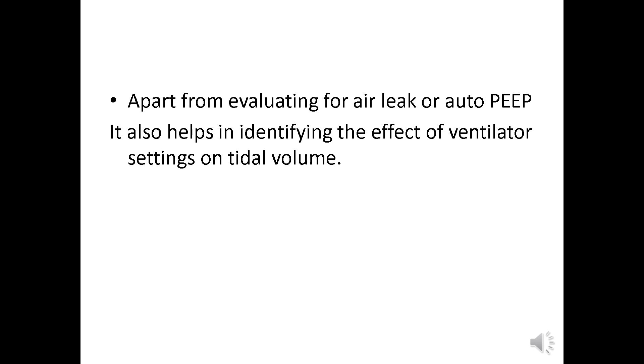Apart from evaluating air leak or auto-PEEP, the volume-time scalar is also very effective in identifying the effect of ventilator settings on tidal volume. For example, if you have increased the pressures in your ventilator settings, the volume-time scalar will show the resulting change in volume — that is, the effect of the ventilator setting on tidal volume.